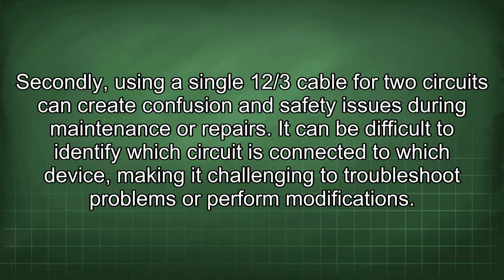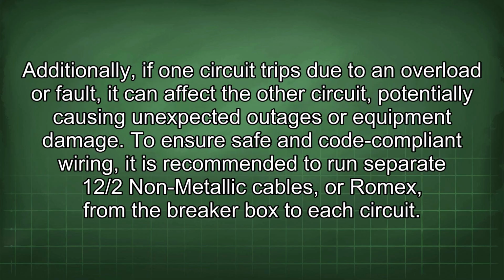Secondly, using a single 12/3 cable for two circuits can create confusion and safety issues during maintenance or repairs. It can be difficult to identify which circuit is connected to which device, making it challenging to troubleshoot problems or perform modifications. Additionally, if one circuit trips due to an overload or fault, it can affect the other circuit, potentially causing unexpected outages or equipment damage.